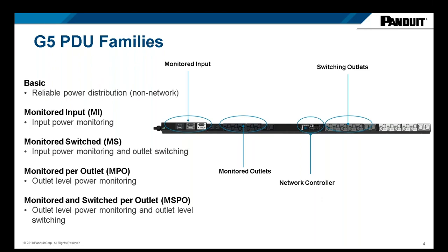From an intelligent PDU standpoint, Panduit offers the 4 main intelligent PDUs desired by the marketplace. There's a monitored input, where you're effectively monitoring at the input plug plus the breakers. There's a monitored switch, which builds upon the monitored input level, where you're able to monitor the power at this level and also switch PDUs, switch outlets. And then there's the monitor per outlet - this one goes to that next level of monitoring, where you're not only monitoring at the input level but also at the outlet level.